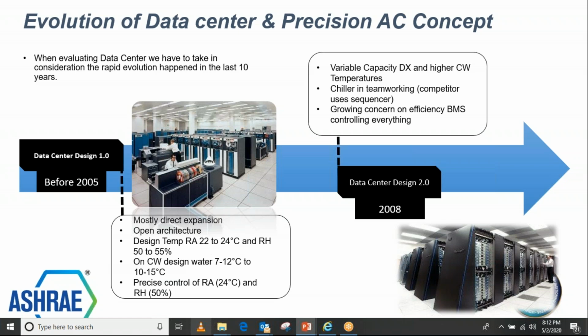And the user who used to always maintain these machines at 22 was concerned for the unit temperature, not the temperature in front of the VFD, the server, the panels, the control room equipment, or the application. They were more concerned about the return air temperature in the cooling unit. But that really was not the concern. At the same time, in chilled water systems, 7/12 water was used in data centers, and at most outside India we used to hear of some applications around 10 to 15, and RH and temperature used to be around this range. So this was the kind of control which people used to have on the return air.